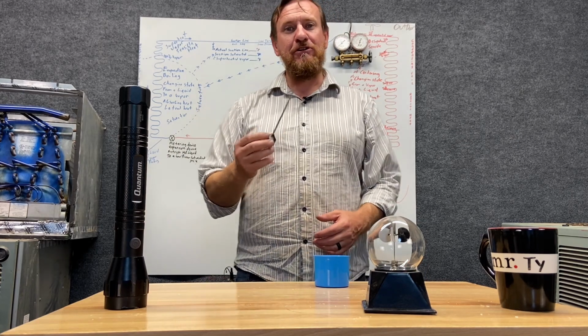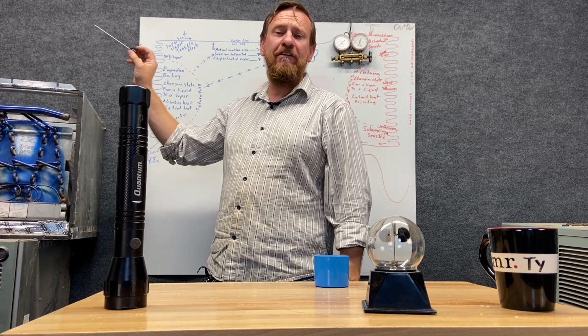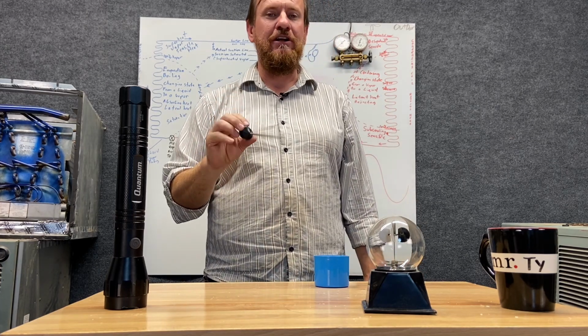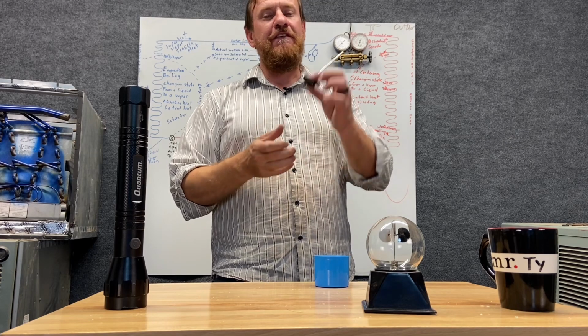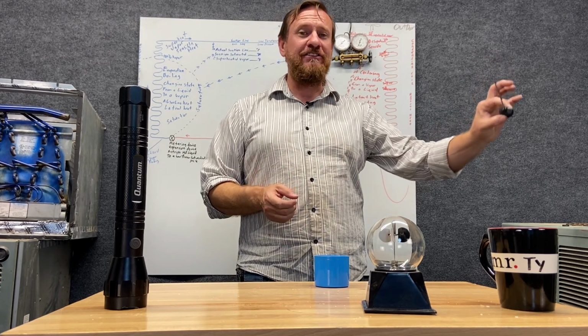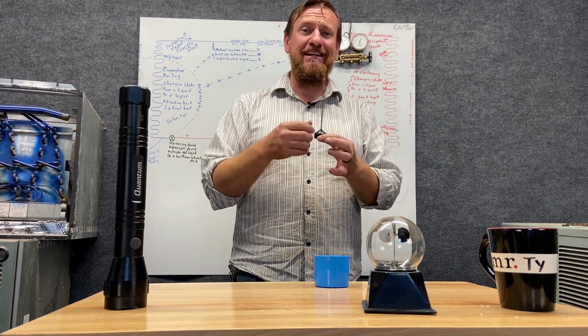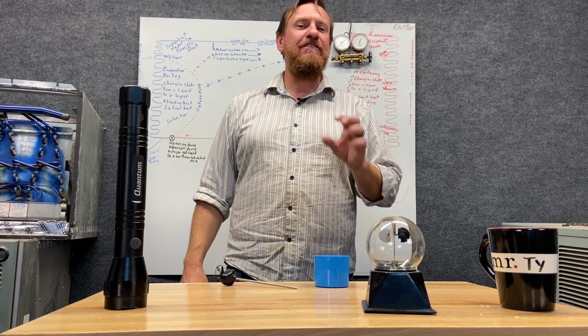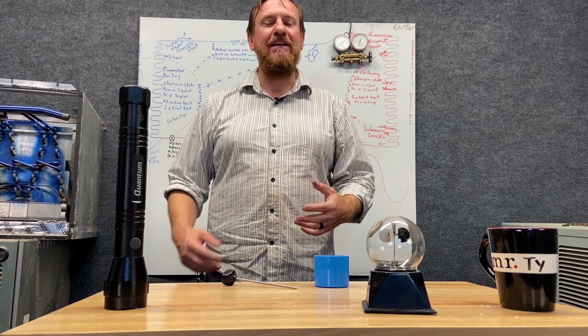When we're taking our temperatures, we want to take our temperature far enough away from an object that we're getting true air temperature and we're not picking up a radiant temperature, because that will throw our numbers off. If you've ever taken a thermometer and put it actually into the sun, it can ruin it very quickly, because all that radiant heat will damage the thermometer in no time. So radiant energy is a very important thing to think about with heat size.